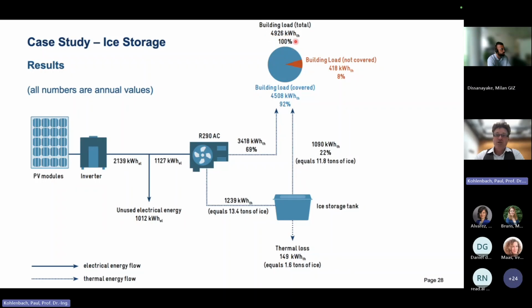So if that equals 100% of air conditioning building load per year, then we can see that the combination of direct air conditioning operation and nighttime operation of the ice storage comes to 92% of this annual building load. So only 8% of the annual building load cannot be covered because there is no sun and the ice storage tank is empty. 92% of the annual building load can be covered either by direct operation or by operation via the ice storage tank. You know, nothing goes without losses. If you have an ice tank somewhere in a hot climate, some of it is going to melt.